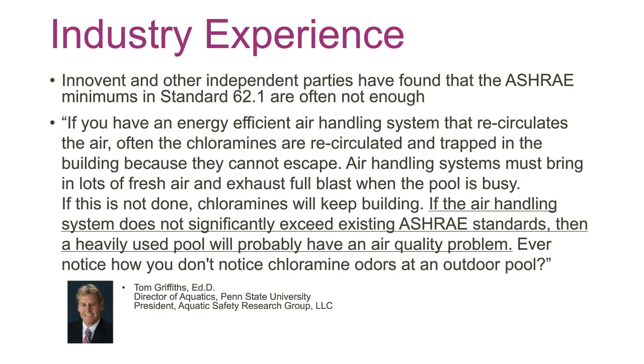Others have experienced the same thing. There's a quote here from the aquatics director at Penn State University, and which you can read, but the gist of it is if you're using a recirculating type system, you're not getting rid of the chloramines, and if the air handling system doesn't significantly exceed the existing ASHRAE standards, then a heavily used pool will probably have an air quality problem. So that really has been the case that we have seen in our experience, both retrofitting systems and in supplying our own and figuring out where the outside air needs to be.